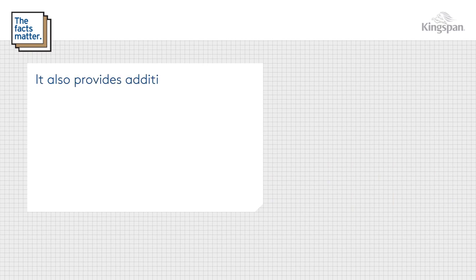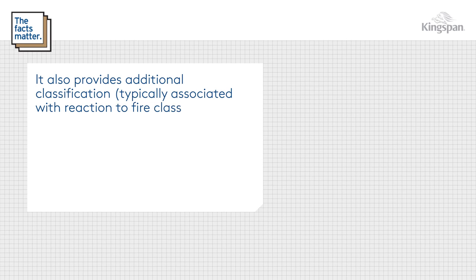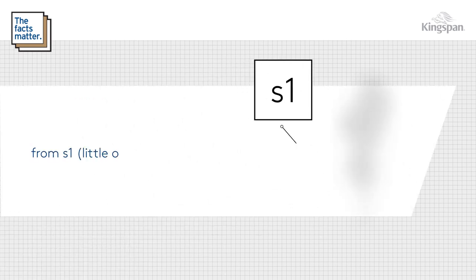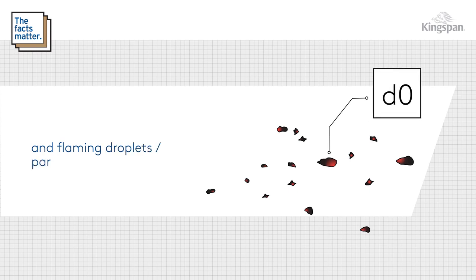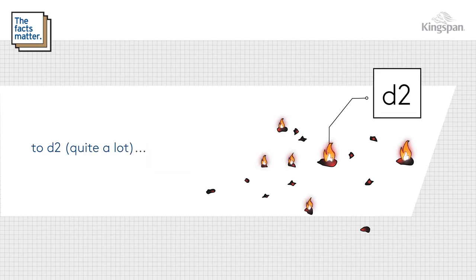The Euroclass system also provides additional classification, typically associated with reaction to fire classes A2 through to D, for smoke production — from S1, little or no smoke, to S3, substantial smoke — and flaming droplets and particles, from D0, none, to D2, quite a lot.